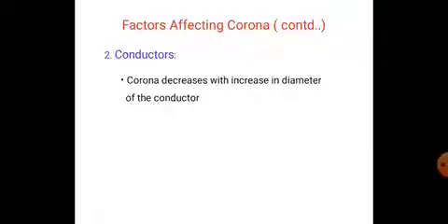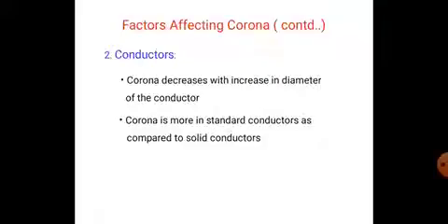The corona decreases with increasing the diameter of the conductor. And the corona is more in stranded conductors as compared to solid conductors. Solid conductor means it is a single conductor. Stranded conductors means more number of conductors. So corona is more in stranded conductors compared to solid conductors.